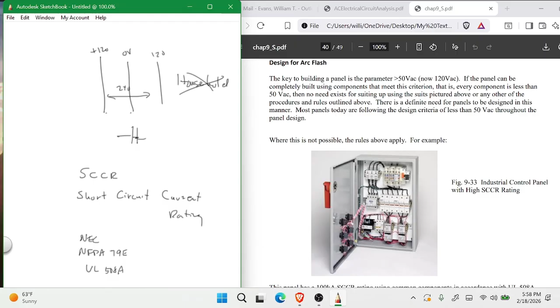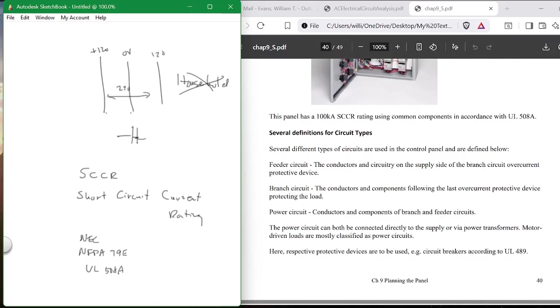This covers all of your wiring in your panel and outside the panel. This covers the rules for when you have to suit up, and this covers how you put that tag or label on a panel - what that label must say, and how to configure the plate that goes on the panel that tells you how it works. So those three: National Electric Code (latest edition), NFPA 70E, and UL 508A.